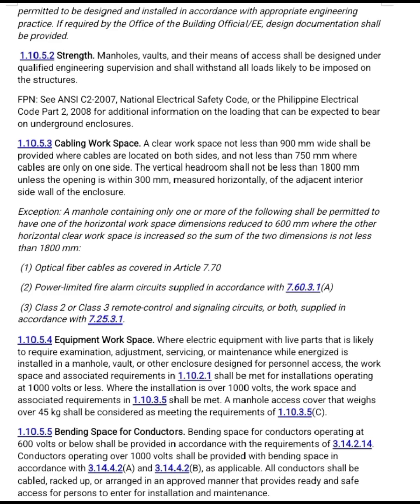1.10.5.4 Equipment workspace, where electrical equipment with live parts that's likely to require examination, adjustment, servicing, or maintenance while energized is installed in a manhole, vault, or other enclosure designed for personnel access. The workspace and associated requirements in 1.10.2.1 shall be met for installations operating at 1000 volts or less. Where the installation is over 1000 volts, the workspace and associated requirements in 1.10.3.5 shall be met.